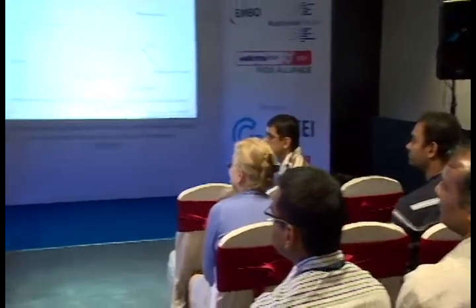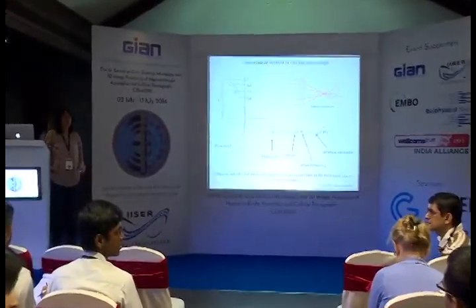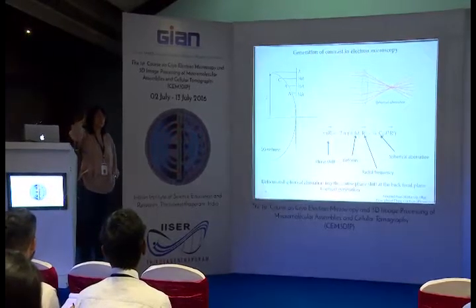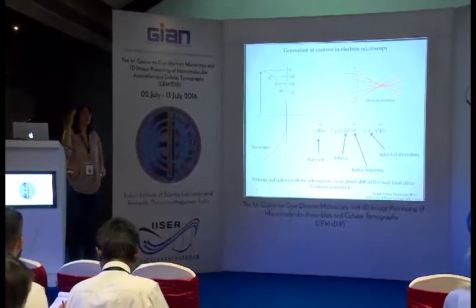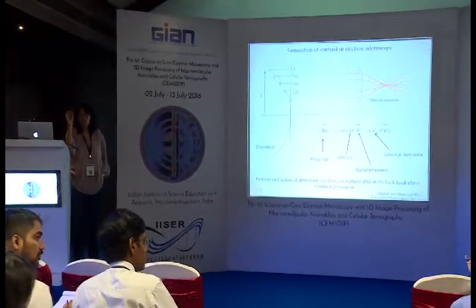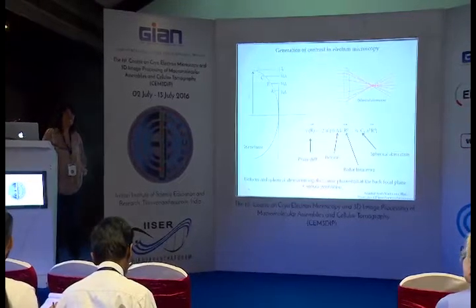Regarding combining phase plate and energy filter: yes, it is absolutely possible to have a microscope fitted with both a phase plate and an omega filter, which can further improve contrast. The in-column filter is generally better than the post-column filter at removing inelastically scattered electrons. Whether a microscope can be retrofitted with a phase plate or energy filter is something still being investigated.